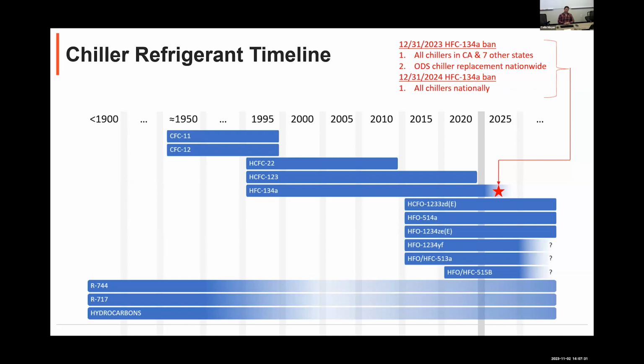It was banned by the EPA under SNAP, the Significant New Alternatives Policy, which was a program the EPA had to phase out the ozone depleting refrigerants. Because the EPA used SNAP to attempt to regulate 134A, it ended up being partially vacated by the U.S. Federal Court of Appeals. Following that, California and 7 other states at the time this slide was put together, but I think maybe about a dozen other states now, decided to enact the same regulations that the EPA attempted to put in place and put a ban on any refrigerant with a global warming potential of 750 or above. And that's going into effect at the end of this year.